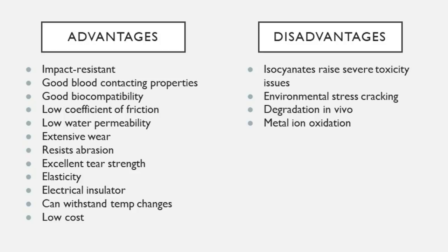Polyurethanes have a number of distinct advantages: they're impact resistant, have fantastic blood compatibility — making them excellent for artificial hearts or ventricular assist devices — and great biocompatibility overall. They have a low coefficient of friction, low water permeability, can withstand extensive wear and vibration, and have excellent tear strength, elasticity, and electrical insulation (hence their use in pacemaker leads). They can withstand temperature changes and can be manufactured at low cost. Disadvantages include toxicity concerns from isocyanates used in synthesis, environmental stress cracking making them poor for load-bearing applications, and susceptibility to in vivo degradation and metal ion oxidation.